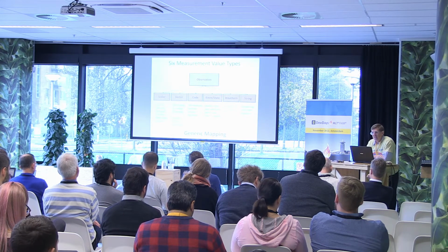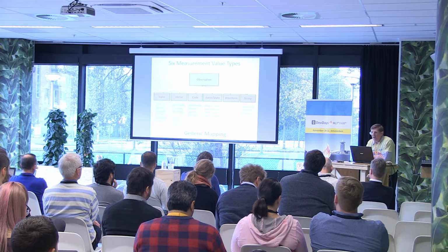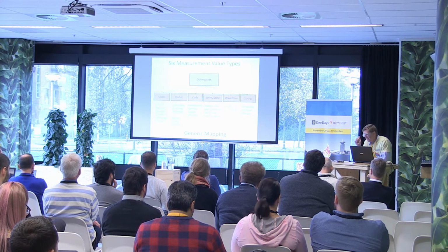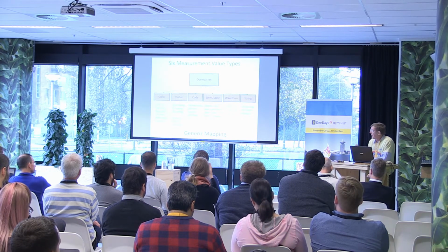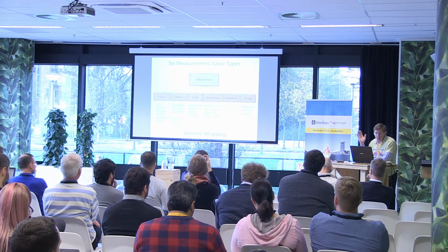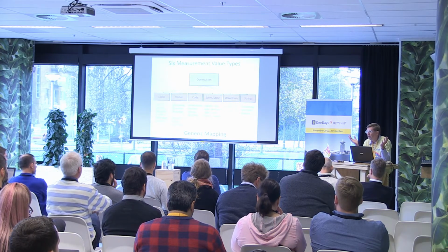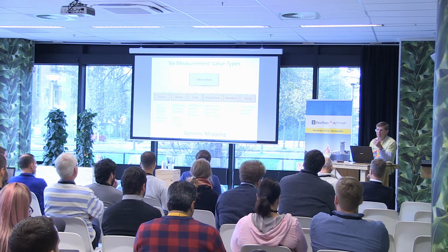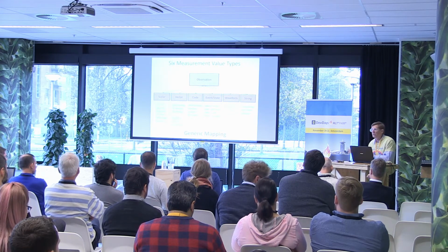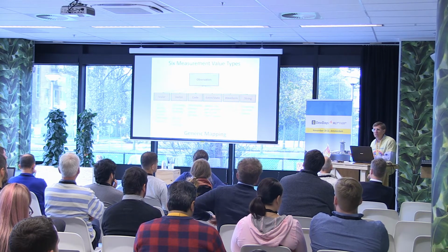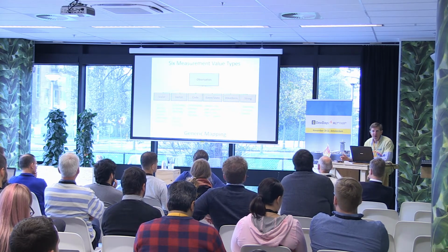This approach, and FHIR basically does the same thing, but this approach of having a generic model for representing measurements has been around for a long time in the IEEE 11073 sets of standards. And what it does instead, it says, what types of measurements, what value types can these devices do? And they can only do 6, at least personal health devices. One of them is a simple scalar. These are the ones that are most common. A temperature, a weight, a glucose concentration, how many miles I ran, all those kinds of things that can be represented by a single number.